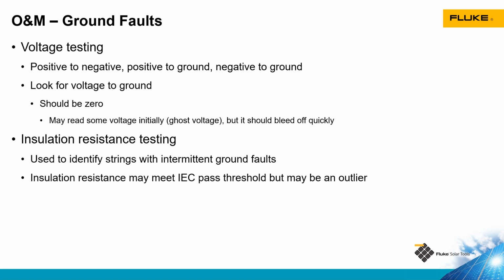You can also use insulation resistance testing to find ground faults. It's very good on circuits that are de-energized when you turn the system off, like our PV output circuit between the combiner box and the inverter, or the inverter output circuit between the inverter and our point of interconnection. You shut the system off, and those should be de-energized. Oftentimes, insulation resistance testing will tell us which circuit has the problem. It's not necessarily going to tell you where the problem is. And sometimes we'll see strings or tests that are still passing according to the IEC standard, which requires about 1 megaohm to pass that insulation resistance test, but the value is less than everything else.